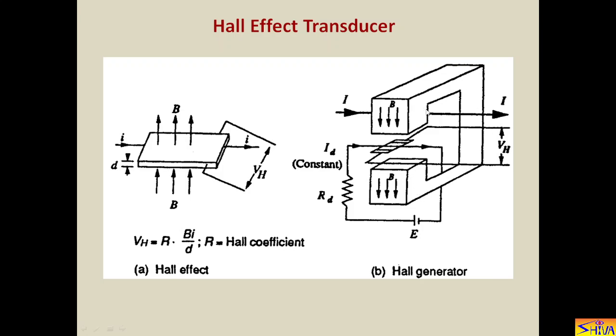This is the magnetic material. When the high current flows, it generates flux and B is the magnetic flux density. Through the Hall transducer semiconductor material, a known DC current Id is passed. Rd is the resistance to limit this current and Id is constant and known. Vh can be measured. From the equation Vh = R·B·i / D, where R is the Hall coefficient, B is proportional to the unknown current I, and D is the plate thickness — all known — we can compute B and hence the unknown current I.